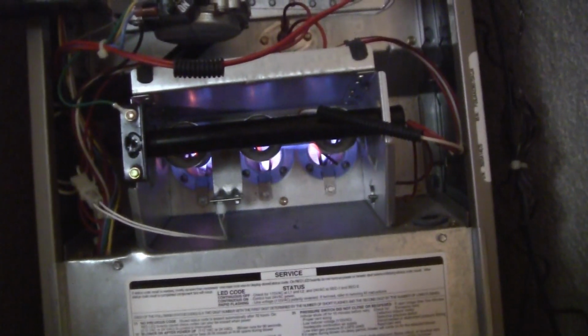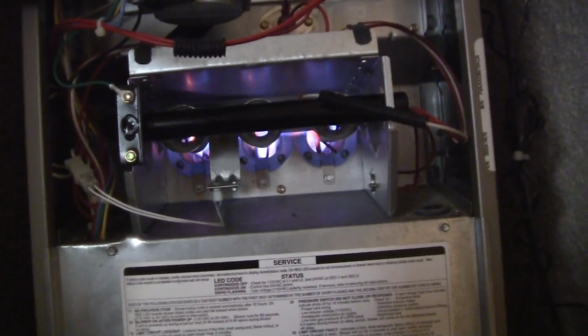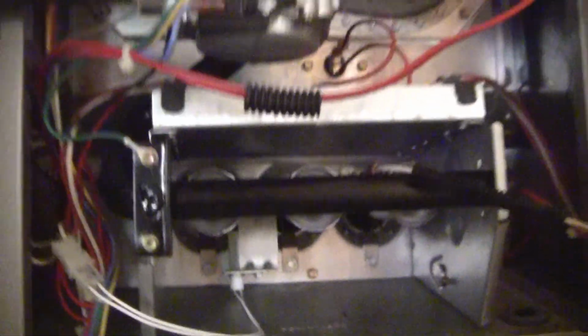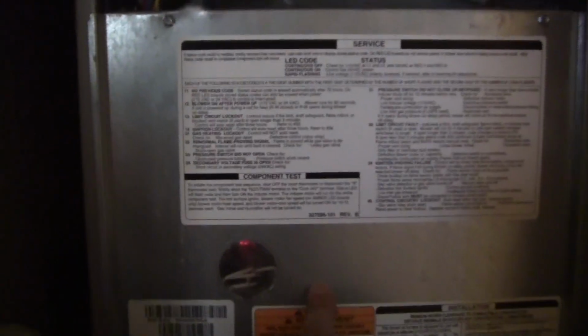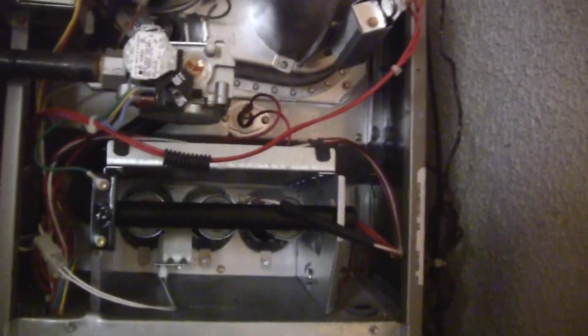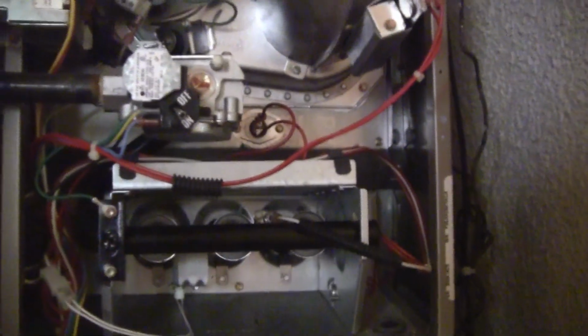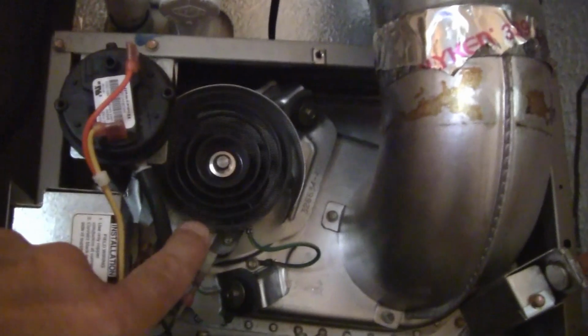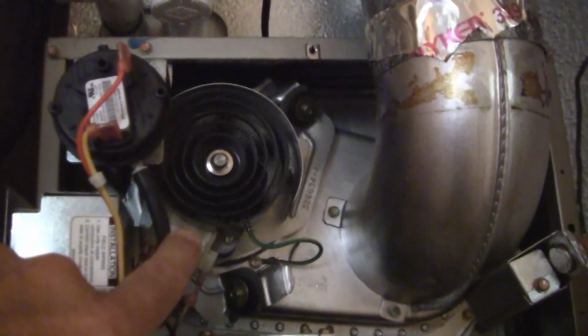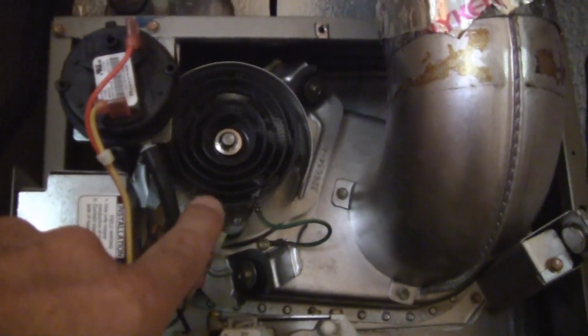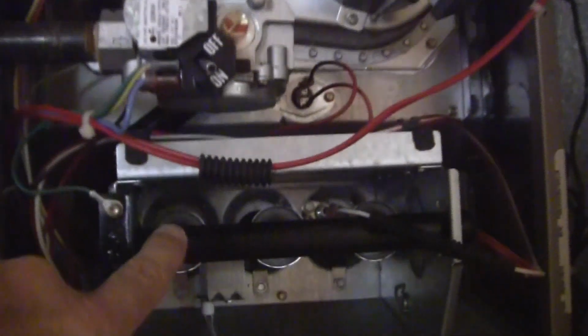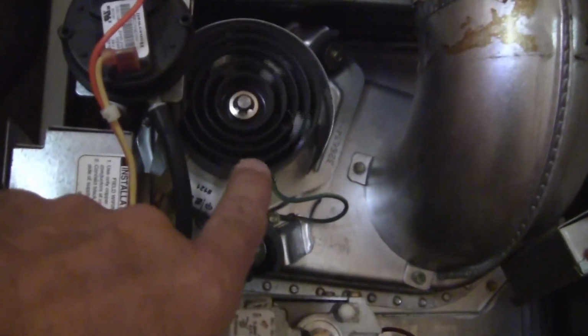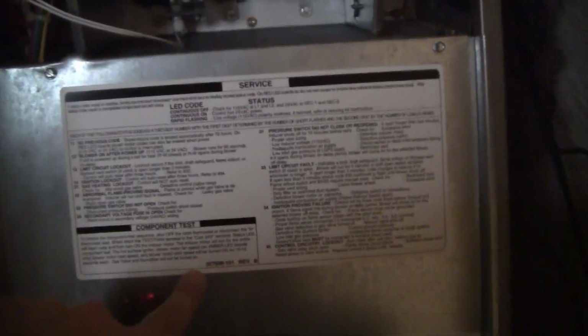My associate is going to shut the furnace off and we'll see the furnace shut down. Go ahead and kill the T-stat. Did you guys see that? First thing that happened was the burner flame shut off, which means that the natural gas valve, the valve right here, shut off, shutting off the flame. The blower motor is still on because the way that the furnace works is that it keeps that blower motor on until the heat exchanger reaches a certain temperature. Also, the inducer fan motor looks like it shut off at the same time as the burner. This is just winding down. It just has a flywheel on it to allow it to coast down slowly. The blower motor is still on, and once it reaches a certain temperature, that will shut off.